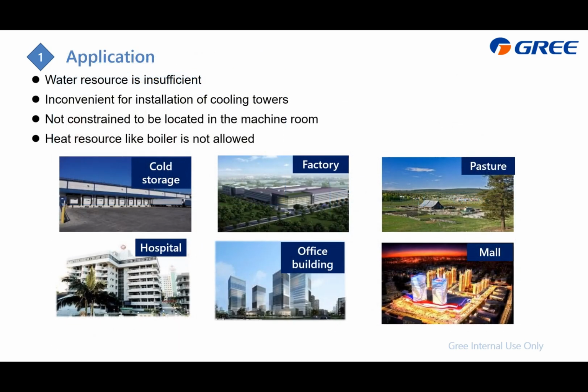For the application of this one, it is air-cooled, which means we don't apply a cooling tower to release heat. It is very suitable and very popular where the water source is not enough, or where it is not convenient to install a cooling tower, or there is not enough room or machine room for the chiller. Then you can consider this air-cooled chiller. And on the other hand, for the heating, there's no need for a boiler.